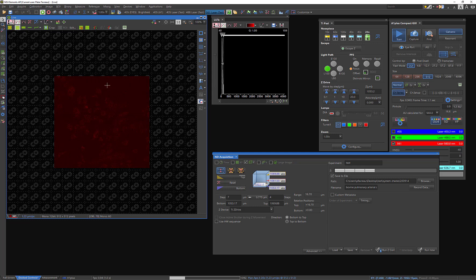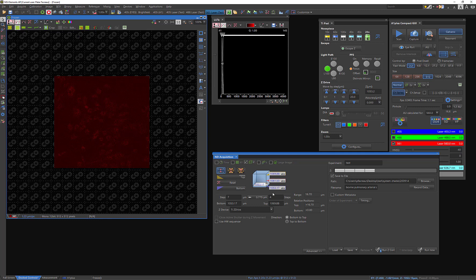So I'm going to click stop, so I'm not continuing to hurt my sample by imaging continuously. And what we see here is that there's a series of positions that have accumulated. The first one here is what I call top. And then the bottom one I just found is right here. And you can tell it to go to the top if you want by just double clicking here, and it'll go all the way to the top. You can tell it to go to the bottom, same thing. And importantly, it's already defined for me what the range is here, 16.7 microns.